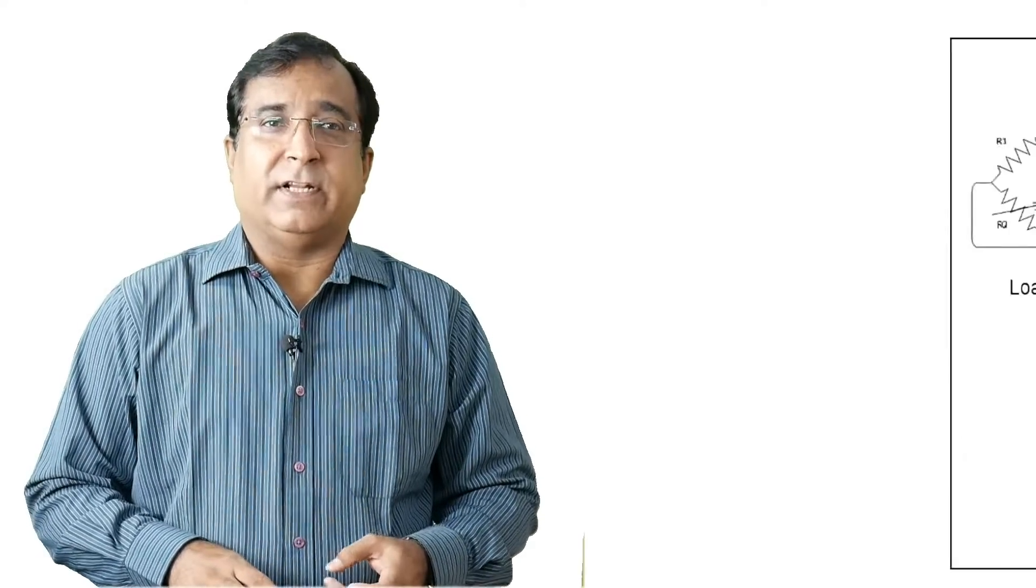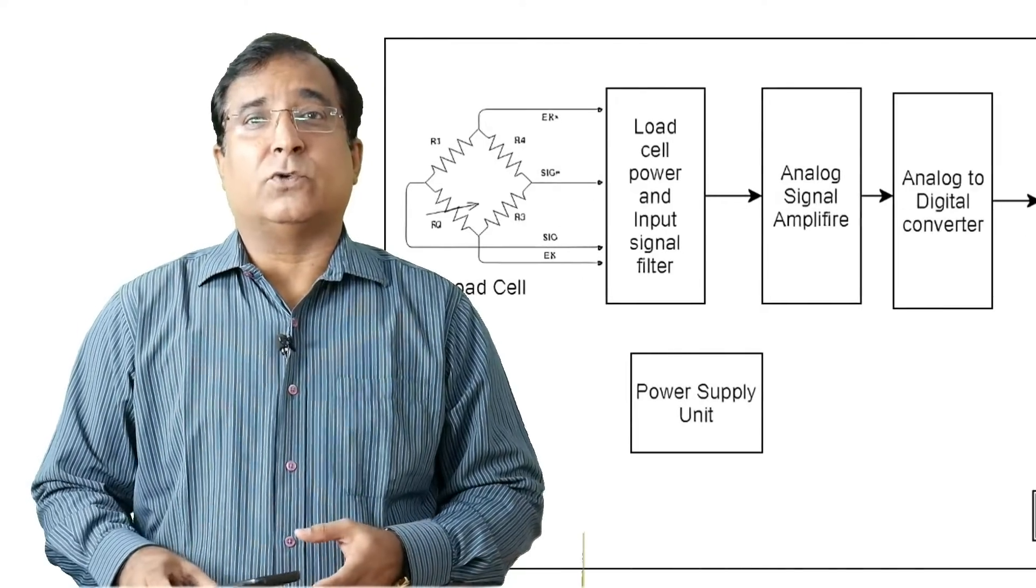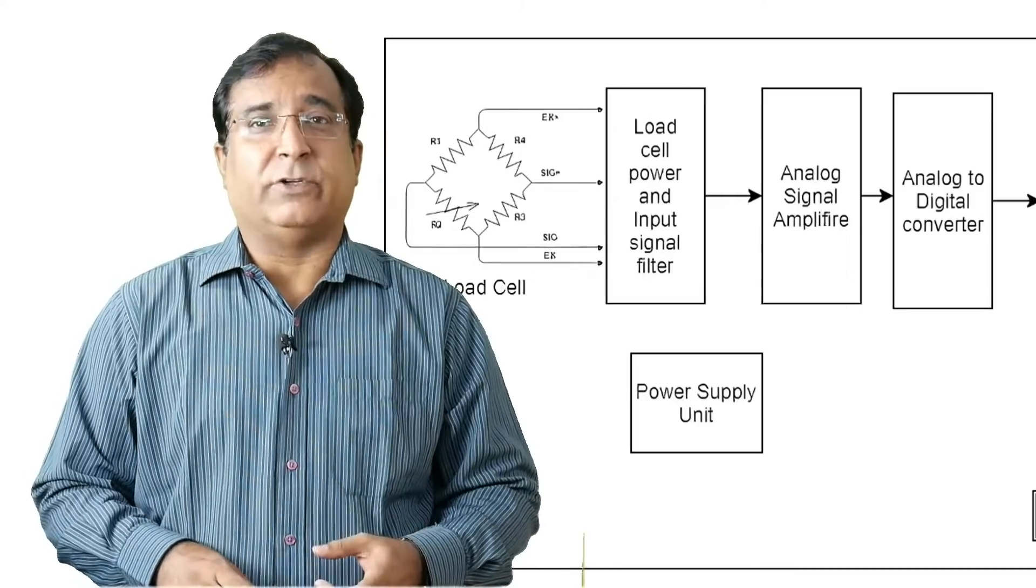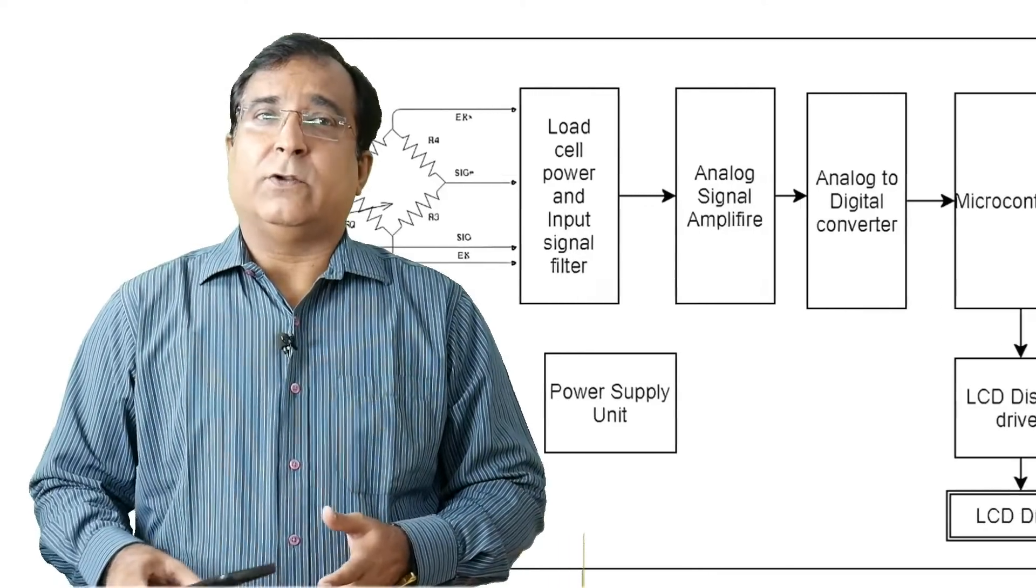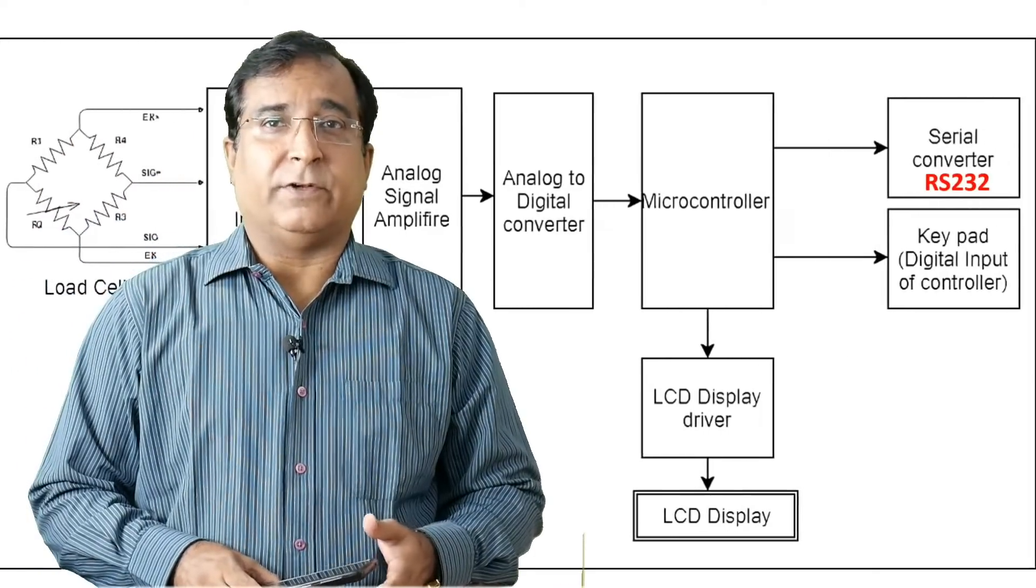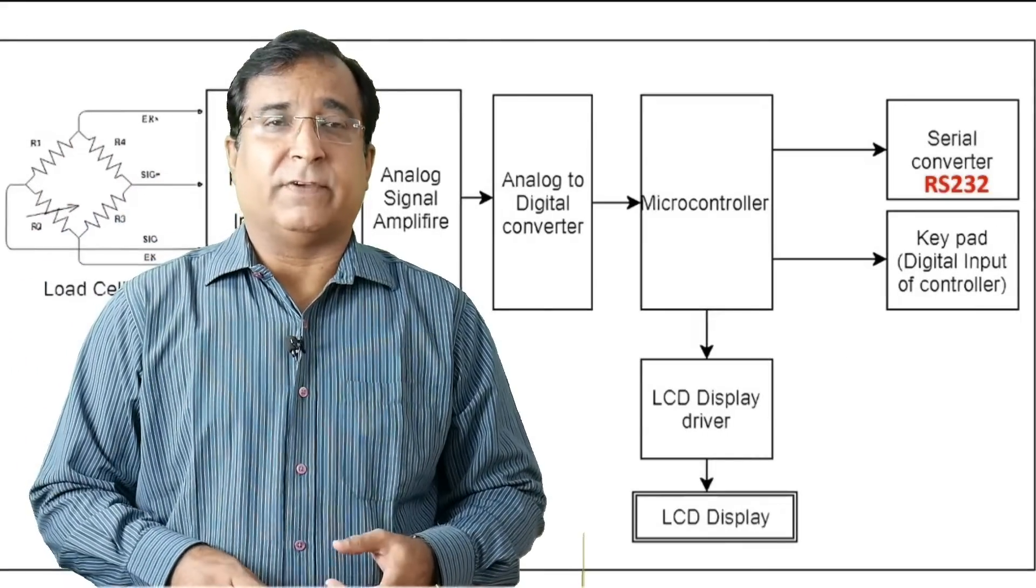The output received in terms of millivolt is converted into physical readings. Here the signal goes through various kind of operations like filtering, amplification, A to D conversion, and then signal goes to digital processing unit for tare and span calibration facility.